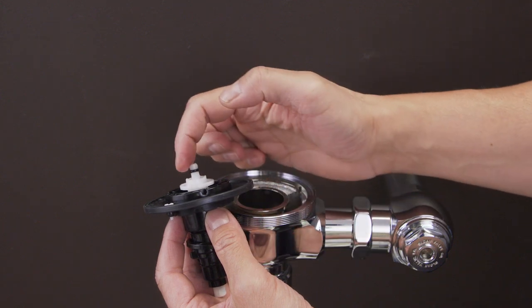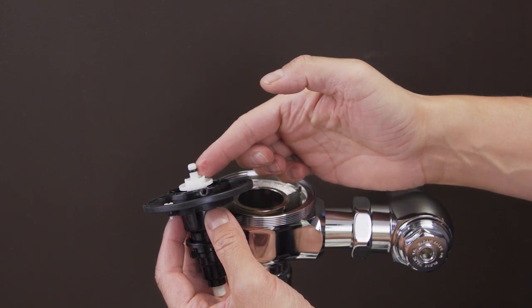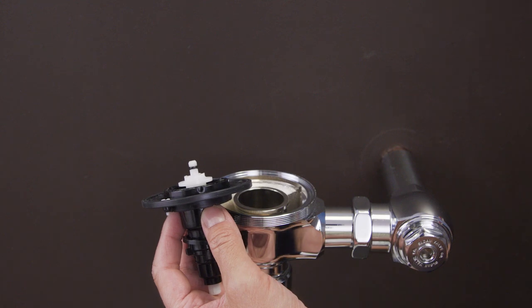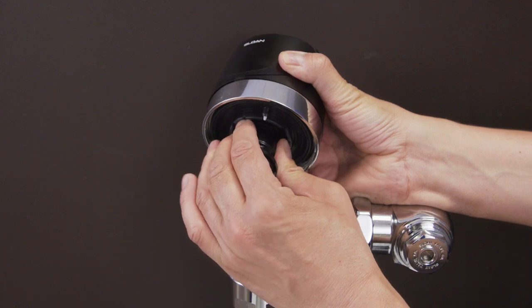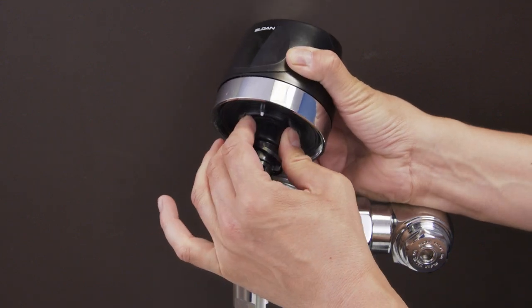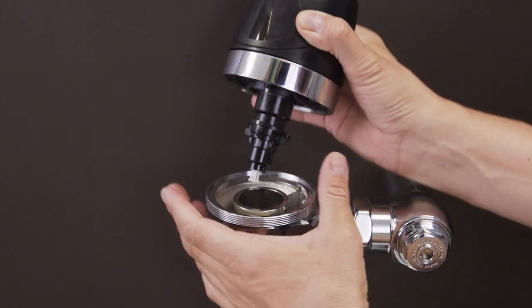Take the diaphragm and put a little bit of water on the flex tube o-ring, as this will make it easier to slide into place. Now twist and push the diaphragm in. When the o-ring works its way into the hole, the diaphragm should hang in place.